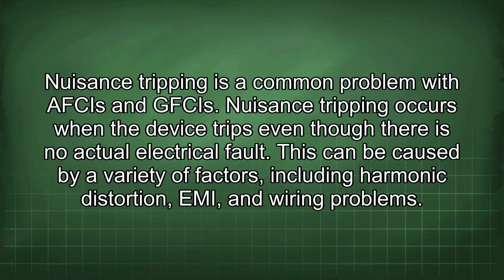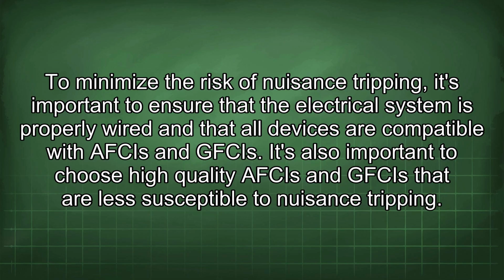Nuisance tripping is a common problem with AFCIs and GFCIs. Nuisance tripping occurs when the device trips even though there is no actual electrical fault. This can be caused by a variety of factors, including harmonic distortion, EMI, and wiring problems. To minimize the risk of nuisance tripping, it's important to ensure that the electrical system is properly wired and that all devices are compatible with AFCIs and GFCIs. It's also important to choose high-quality AFCIs and GFCIs that are less susceptible to nuisance tripping.